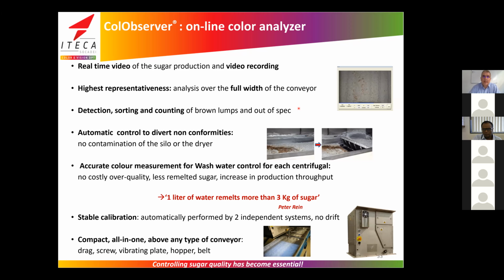The second point is that we may have a big difference in the sugar aspect at the centrifugal because the load is totally different, or the moisture of the sugar is totally different. But usually when we have finished our commissioning, we have found a good correlation with the laboratory. If the laboratory is accurate enough and with good repeatability, we have a system which will follow the laboratory and give the same measurement as the laboratory. But this is a very important point that you have to understand: our system controls all the surface of sugar. The laboratory controls only 100 grams.